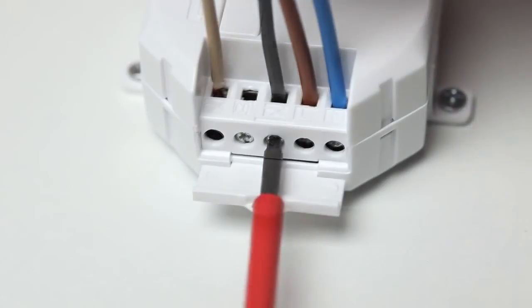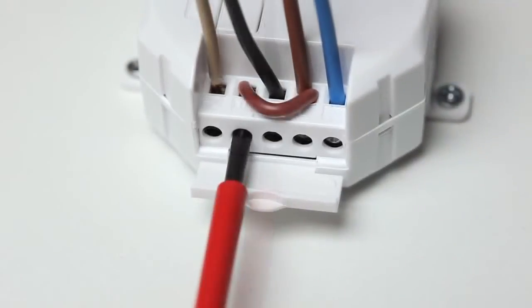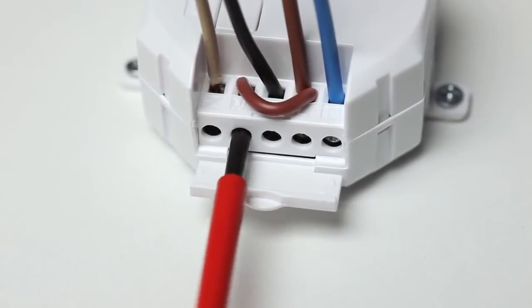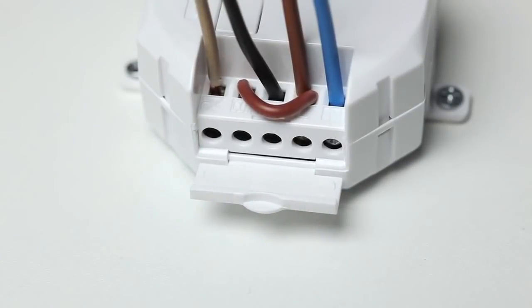Connect the open-closed circuits to control the motor. If the motor is mains powered, you need to link the L terminal to the common terminal on the relay output side. The N feed can be fed directly to the controlled motor.